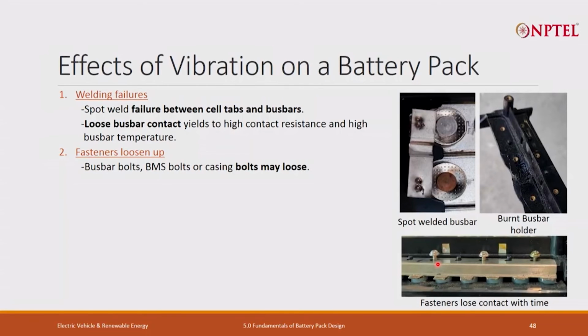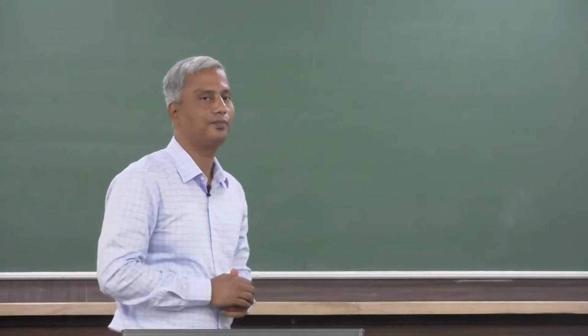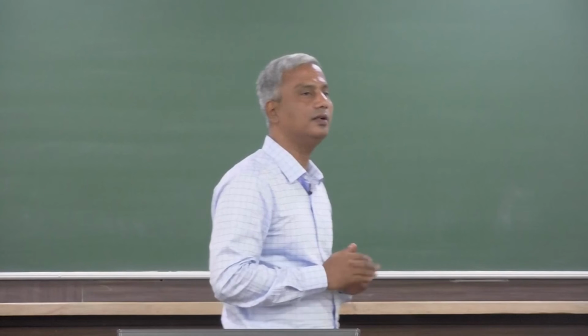Because of vibration, if your thread design is not proper, the fasteners connecting the multiple bus bars together, or connecting the packs, will start loosening up. Let's take the example of a bus bar. If it starts loosening up, what will happen? The contact area will start reducing.